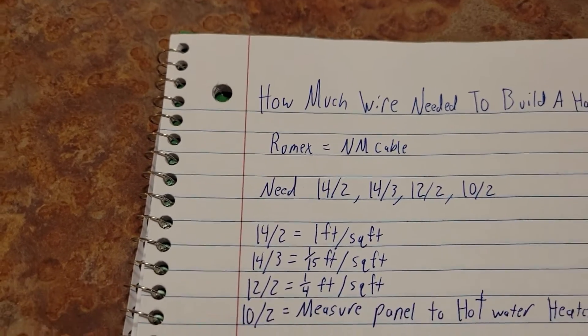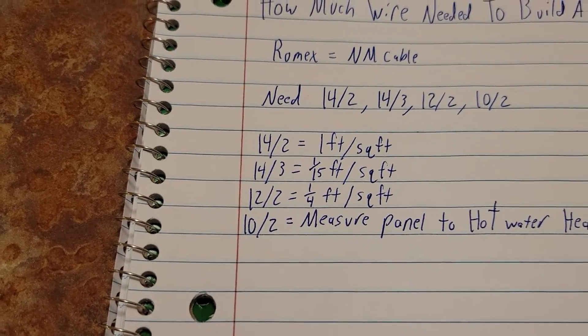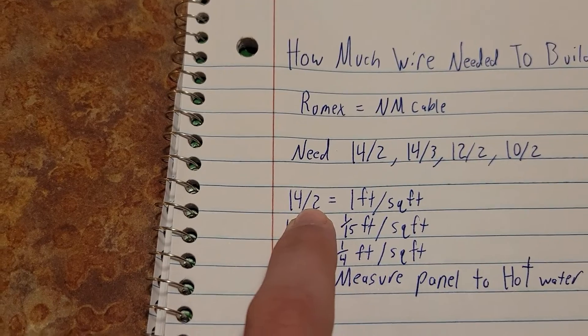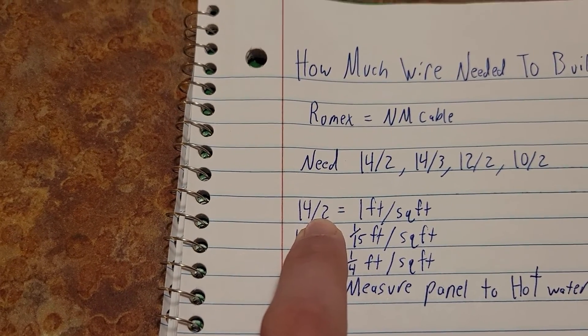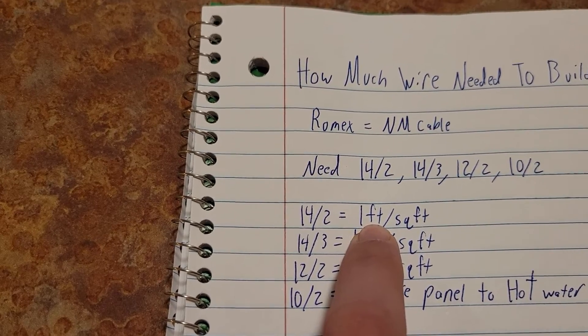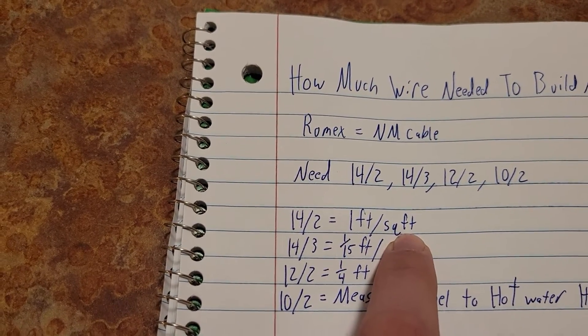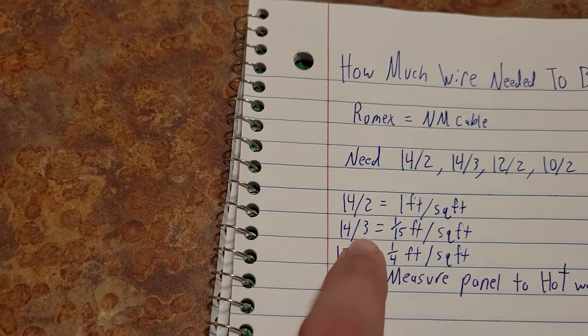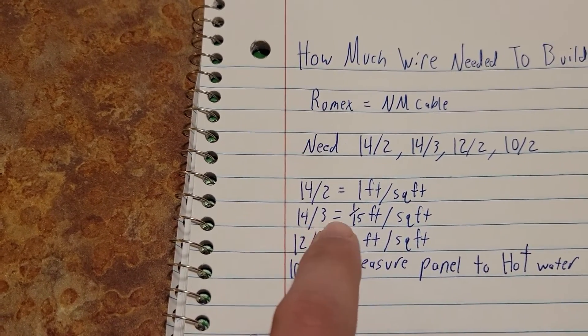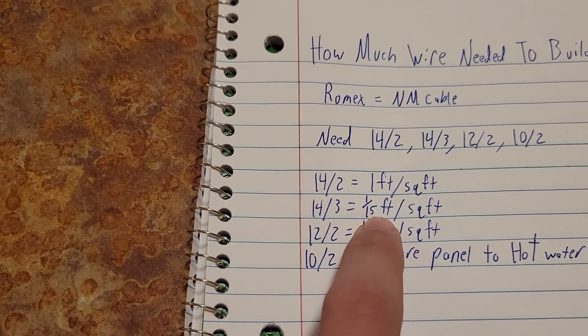Now we've got a few formulas here that you're going to need to know. To get the amount of 14/2 you need, you're going to multiply 1 foot of 14/2 times the amount of square feet in the house. To get the amount of 14/3 you're going to need, you're going to multiply 1/15th of a foot per square foot of the house.